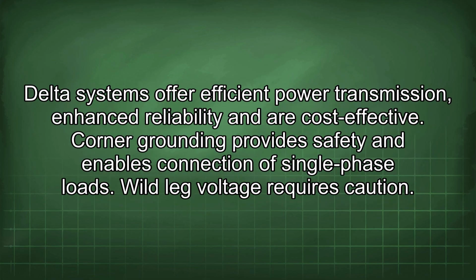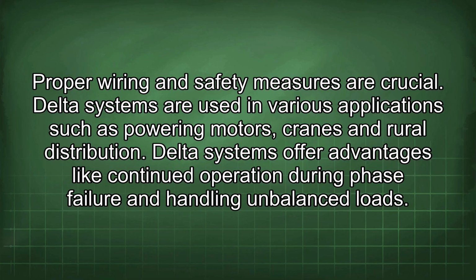Delta systems offer efficient power transmission, enhance reliability, and are cost-effective. Corner grounding provides safety and enables connection of single-phase loads. Wild leg voltage requires caution. Proper wiring and safety measures are crucial. Delta systems are used in various applications such as powering motors, cranes, and rural distribution. Delta systems offer advantages like continued operation during phase failure and handling unbalanced loads.